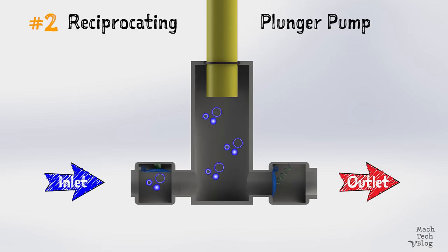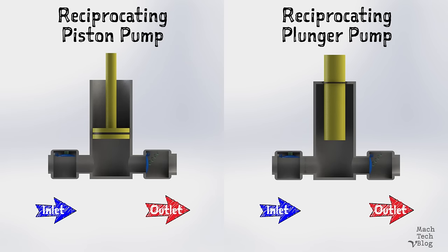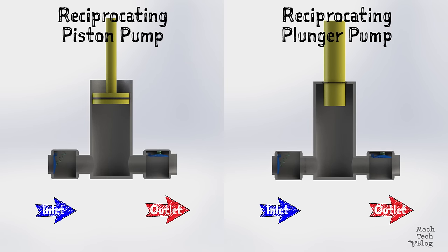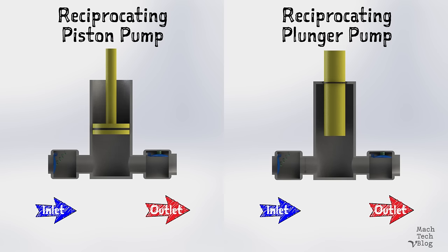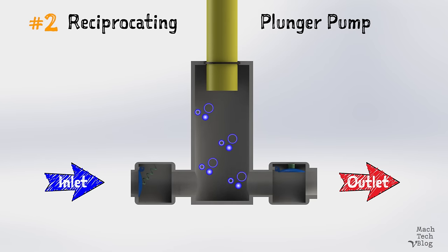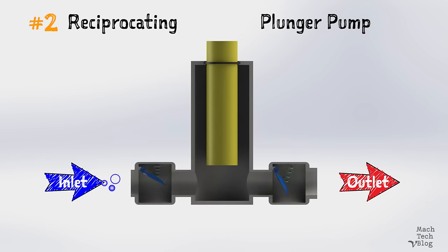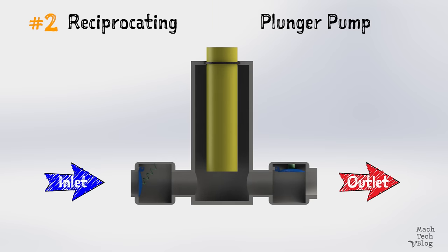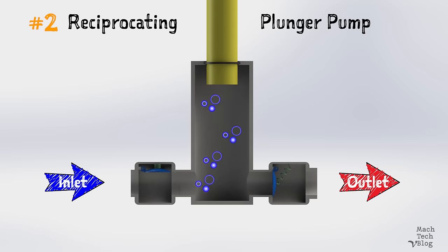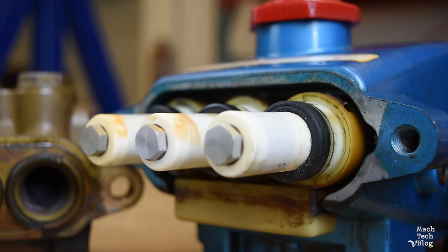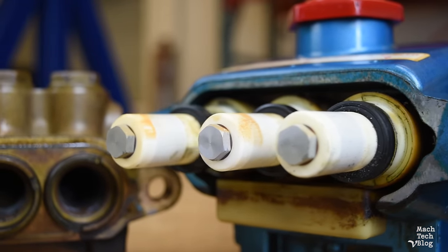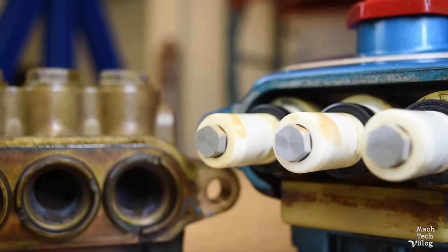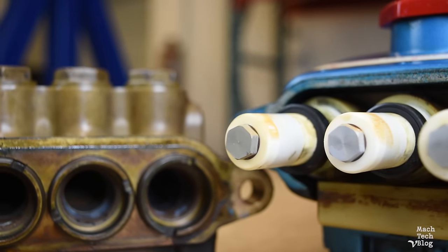Pump number two is the plunger pump. Plunger pumps look very similar to piston pumps, but they work a little differently. Unlike a tight-fitting piston, a plunger fits loosely in its cylinder. Just like when your bathtub overflows because you filled it too full with water before jumping in, the physical mass of the plunger alters the size of the chamber and displaces the fluid. This is a triplex plunger pump, which uses three staggered plungers for smoother flow delivery, but it is otherwise the same as our demonstration.